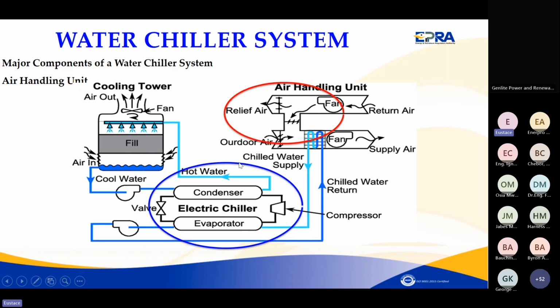Or you can even switch off the chiller if the air outside is suitable. For example, in a data center, you require like 20 degrees. But at night and in cold weather, you find that outside the air is at 14 degrees. You can supply it directly and have it cool the place and exhaust the air outside. You just use the fans. That is an example of what we call free cooling, where you switch off the compressor and use the external environment air to cool the room. Because if you want to achieve 20 degrees and what you're having from outside is 14, 15, up to say 17 or 18 degrees, you don't require the compressor, the refrigeration cycle of the chiller. You're going to see that one as an energy efficiency measure.